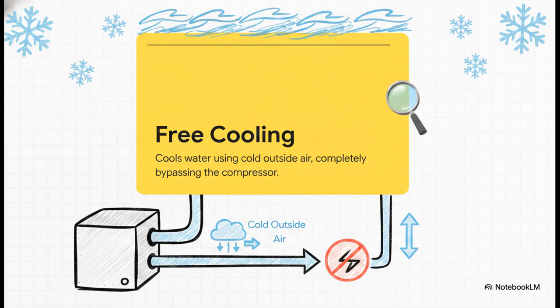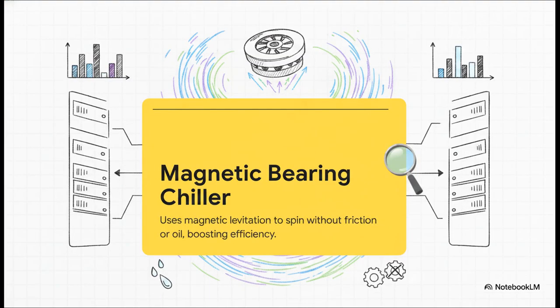So, the crucial innovation here is a feature called free cooling. Imagine it's winter, or even just a crisp autumn day. Instead of firing up that power-hungry compressor we just talked about, free cooling allows the system to use cold outside air to chill the water directly, without running the compressor at all. This dramatically lowers the PUE and completely avoids water waste, making large air-cooled chillers with this feature the absolute hottest new trend in the industry right now. And it gets even cooler.